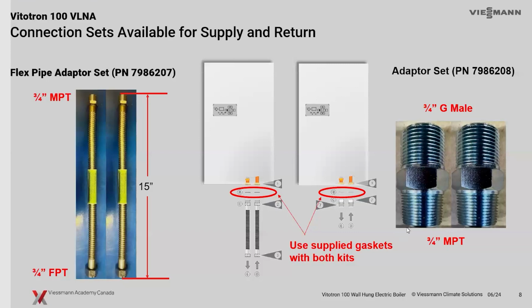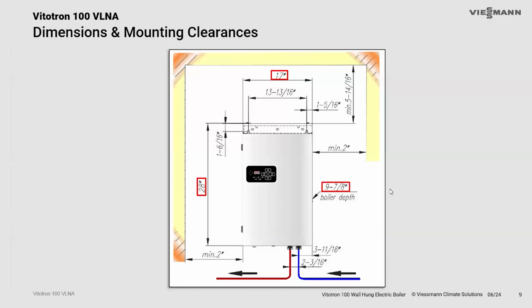Just a note, like I say, we've done it a few different ways here. An NPT to that O-ring is acceptable if you keep it within the copper and some of the PEX and some of the different style fittings that are out there. As far as small boiler, there you go. There's your footprints and some of the distances as far as clearances. In the manual, we show this, but a very small footprint.